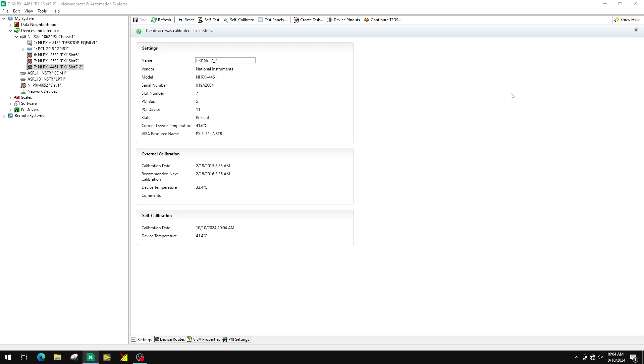After calibration is complete, open the test panels. In the Analog Output tab, you can configure various settings such as voltage output, sine wave frequency, output mode, output configuration, and maximum-minimum outputs, as well as the update rate. For this demonstration, we will use the default settings and click Start.